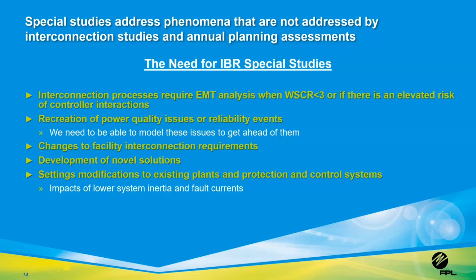We have performed studies with high penetrations of IBR to identify future grid impacts. Some of these studies include speculative generation that would not be captured in interconnection studies or annual planning assessments. We have identified reliability impacts that can be proactively mitigated through changes to our FAC1 interconnection requirements, effectively raising the performance standard of IBRs. For some reliability impacts, we need new solutions that we don't currently have at Florida Power and Light, and I'll give an example of those in the coming slides. And there have also been some cases where we have to modify protection settings at existing solar plants or even existing synchronous generators as well. Next slide, please.